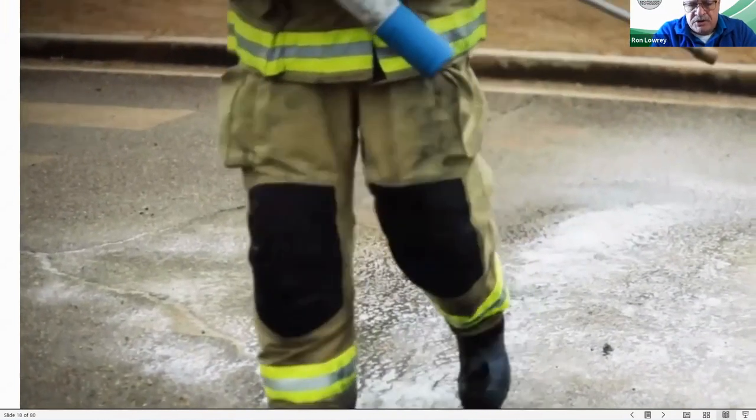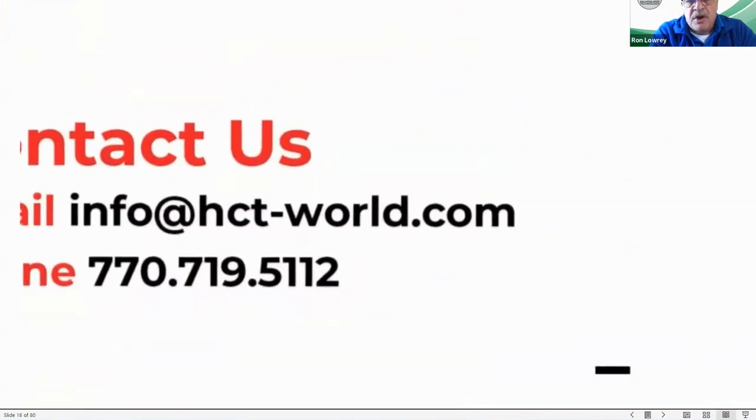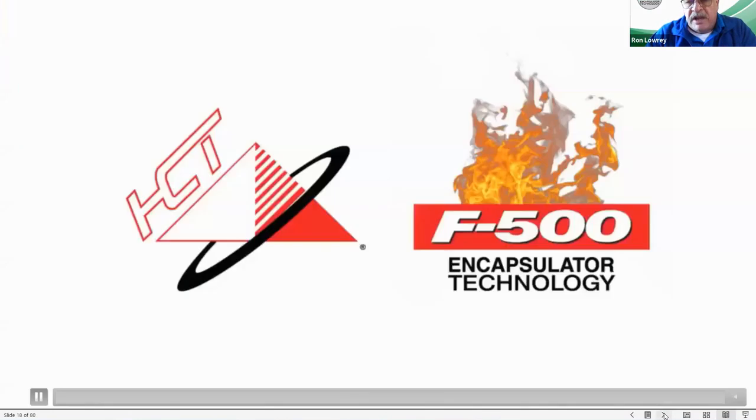So treat that fuel spill, use your 4-gas meter, run it across the surface of the spill. If you have 0 LELs, you know your fuel's encapsulated, you've rendered it inert, and you now have a safe working environment.